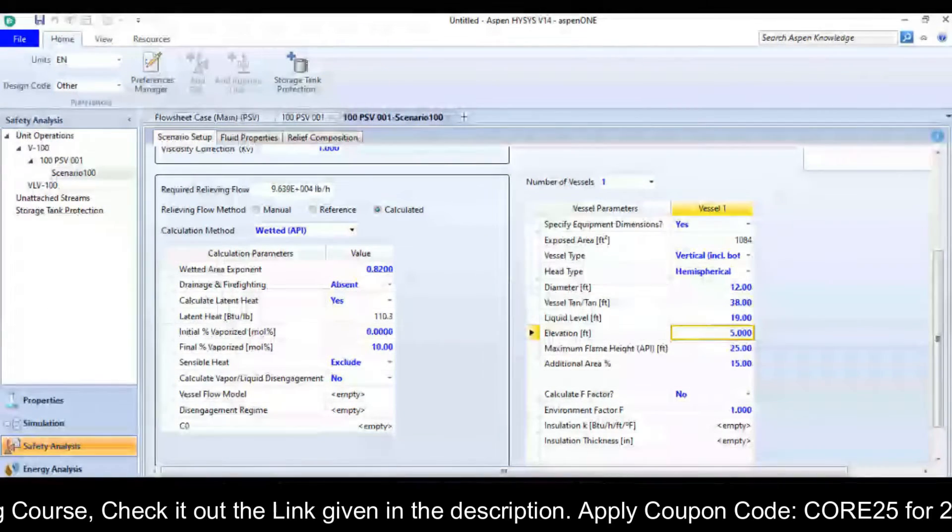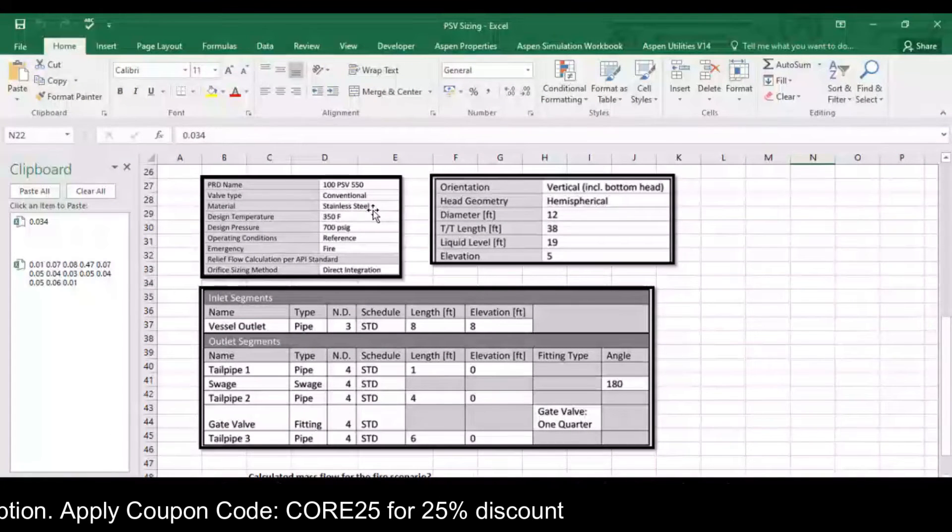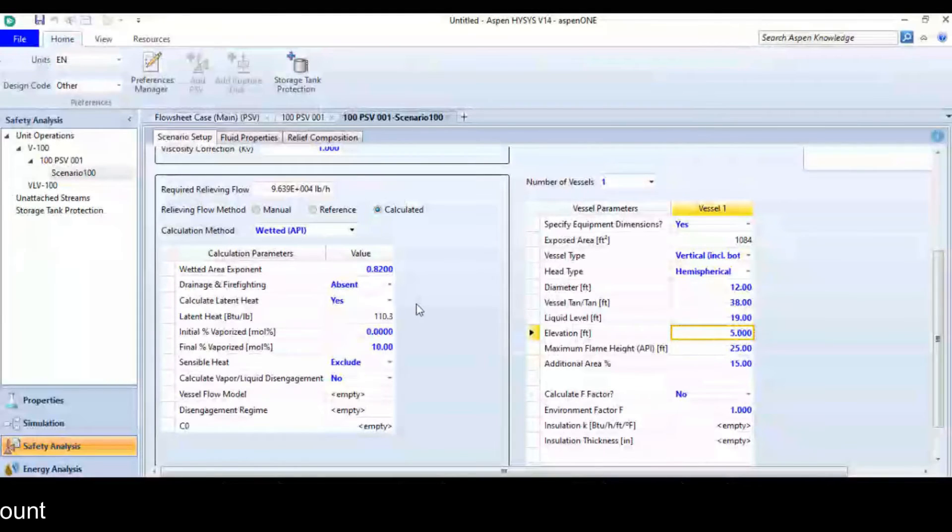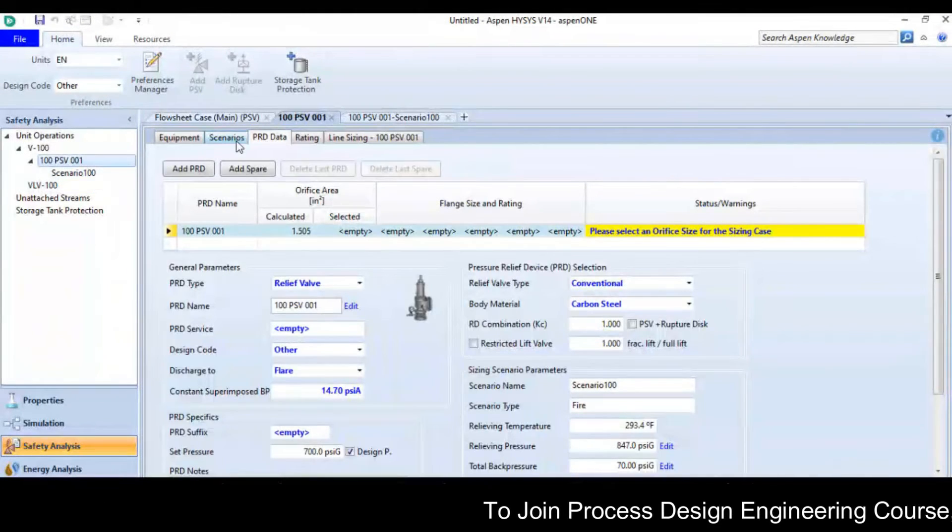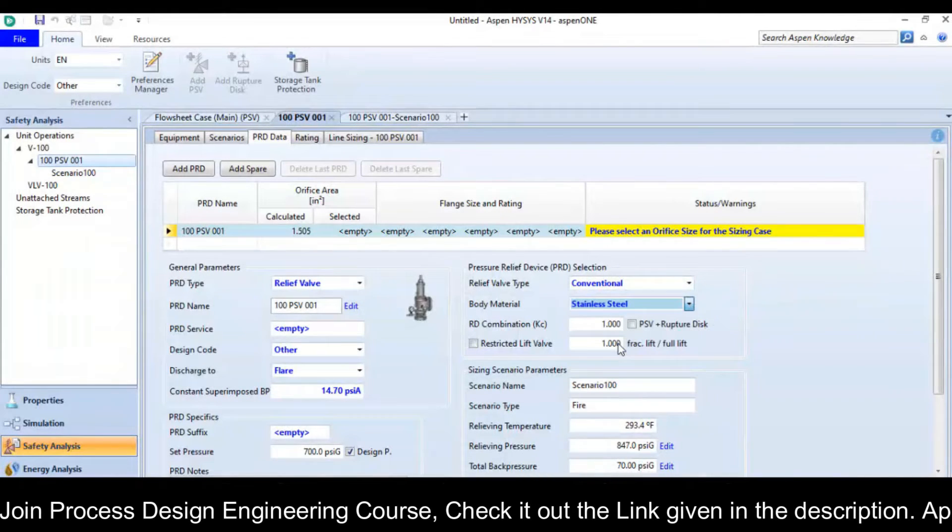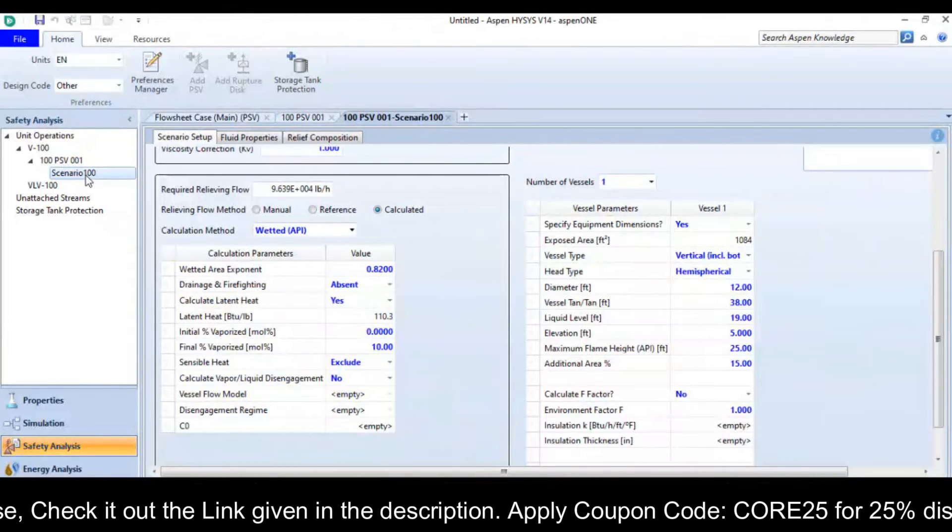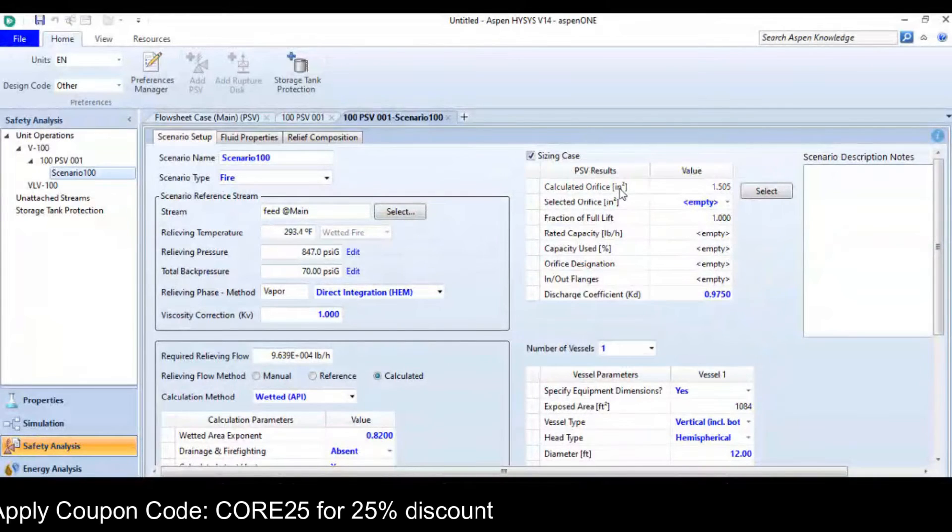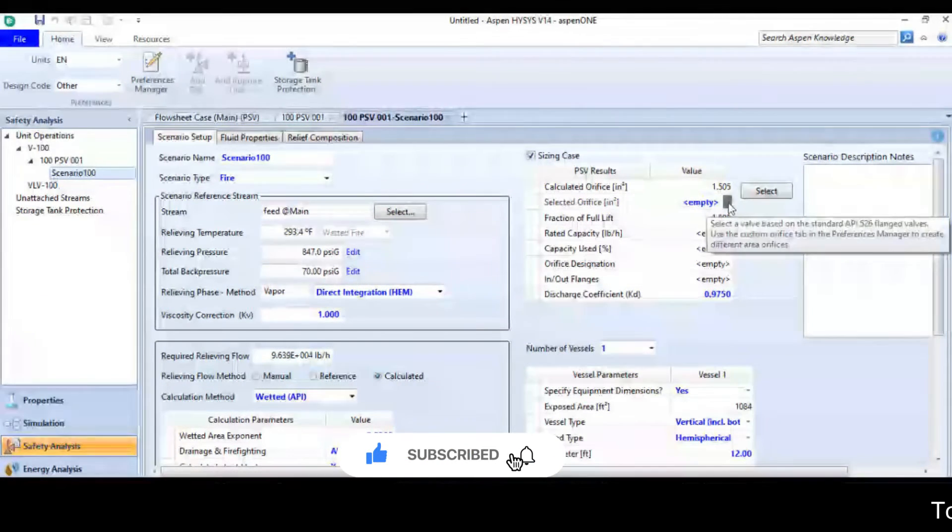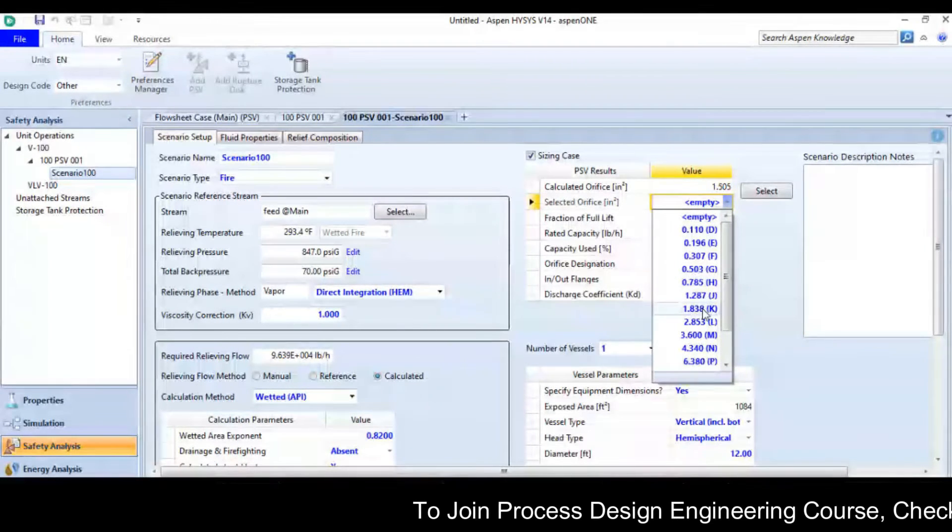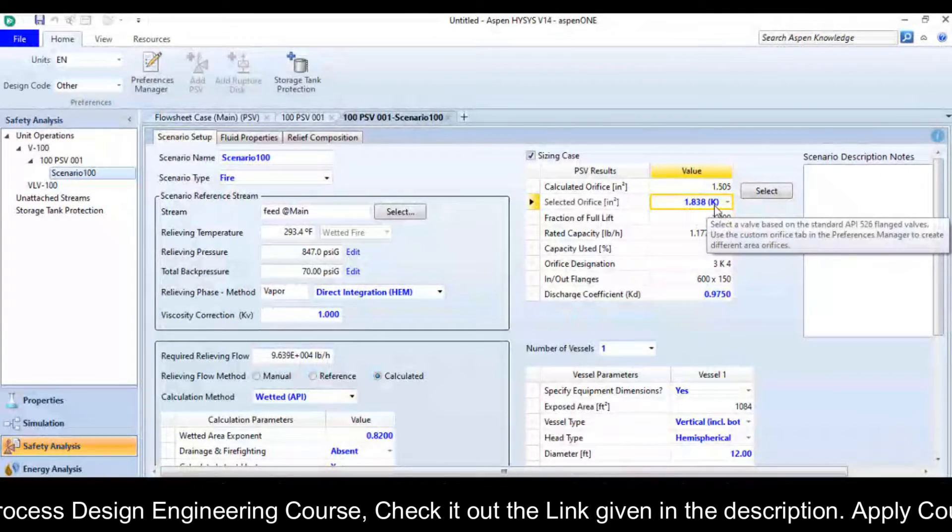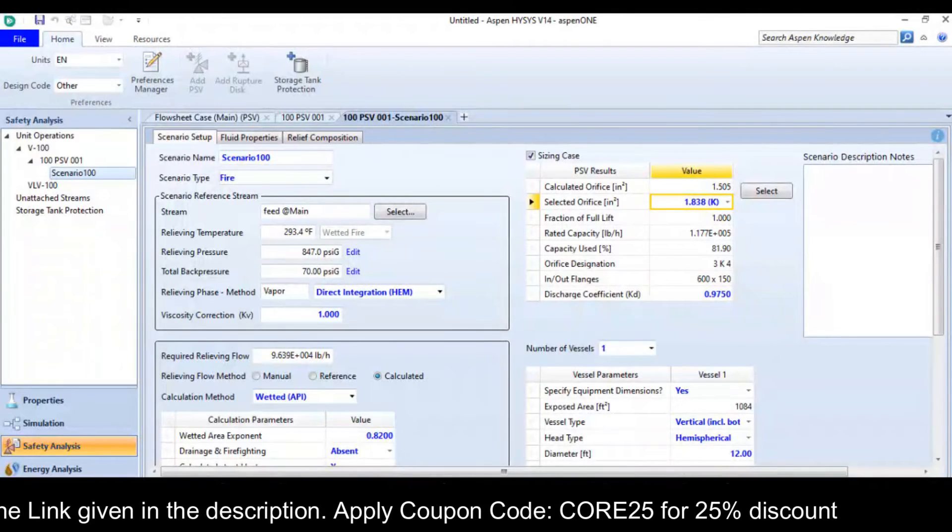After defining all these values, the valve type is conventional and the material is stainless steel, so I need to define it as stainless steel. So I go back to the PSV option, then choose the material here, it is stainless steel. Simply go to scenario and look at this, the calculated orifice size is 1.5. So I will select equivalent or higher size. The next available is 1.838 K. So the designation of the orifice is K and you can see that orifice calculation completed.